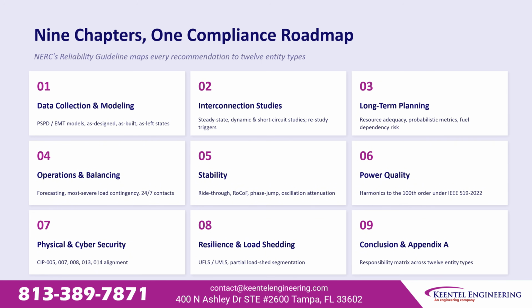NERC organized its recommendations into 9 chapters, each mapped to specific entities: data collection and modeling, covering dynamic models and as-built equipment states; interconnection studies, covering steady-state, dynamic, and short-circuit analysis with new restudy triggers; long-term planning, covering resource adequacy and fuel dependency risk; operations and balancing, covering forecasting and 24/7 contacts; stability, covering ride-through and oscillation attenuation; power quality, covering harmonics to the 100th order under IEEE 519; physical and cybersecurity, aligned to the CIP framework; resilience and load shedding, covering partial segmentation; and a closing chapter, mapping responsibility across all 12 entity types.